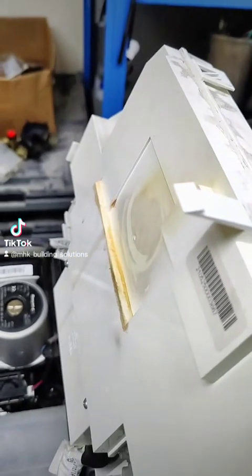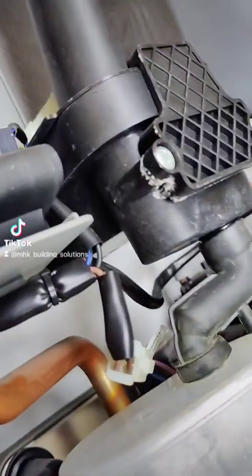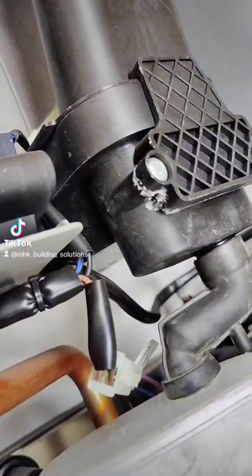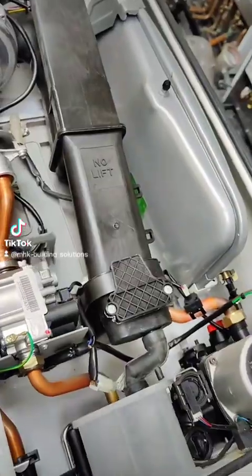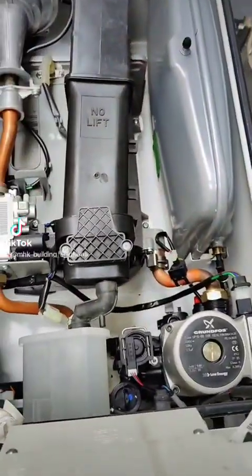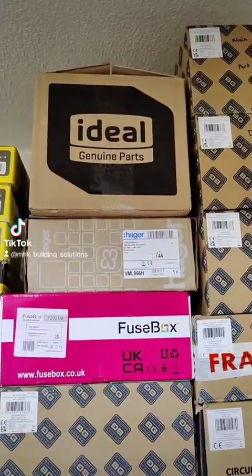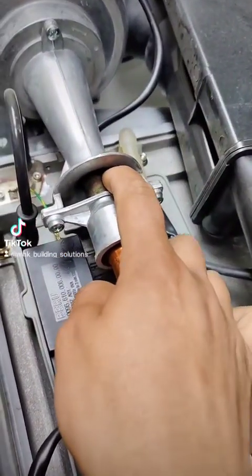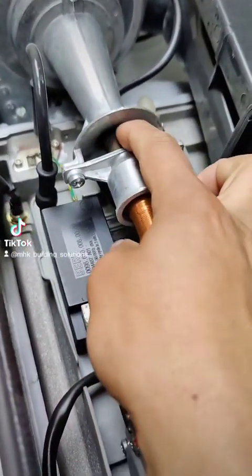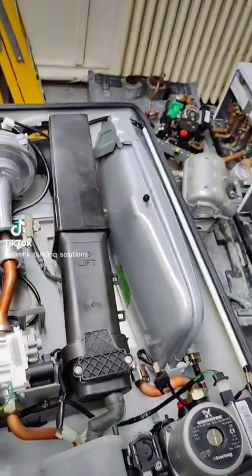That's the problem with the majority of these unfortunately. Can you see all of these marks — heat marks? This is the cause of those marks. Do drop me a line if you've come across this problem before. I've got an ideal sump just in there, a brand new one, because we do often change these. The venturi is quite bad — I don't think it was serviced on a regular basis. So I'll be stripping it all out and showing you as we go along.